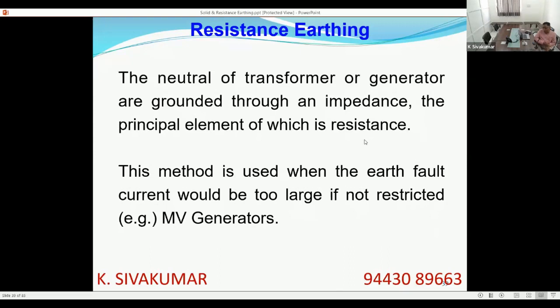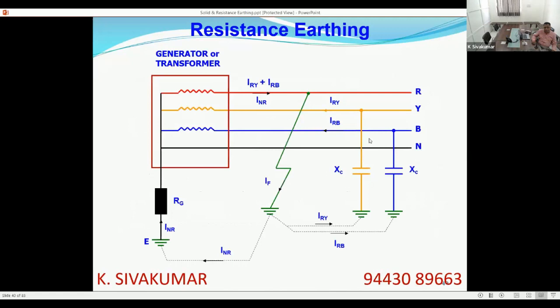The case in point is medium voltage generators. Here I am talking about above 1000 volt up to 35 kV. So, generators above 1.1 kV, because anyhow below 1.1 kV you must solidly earth the generator. Or if multiple generators are there, impedance earthing or neutral switching, we will discuss that in a separate session. But as far as now concerned, resistance earthing is mostly practiced for medium voltage generators.